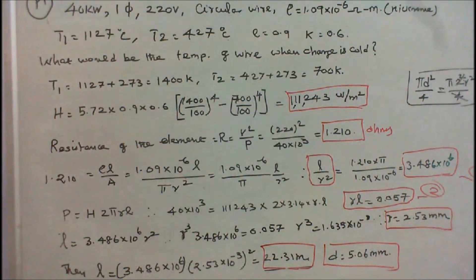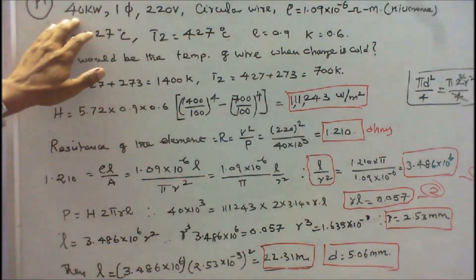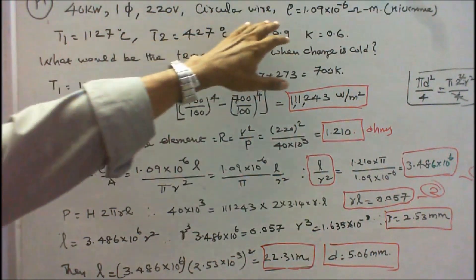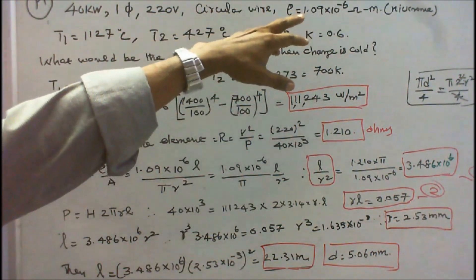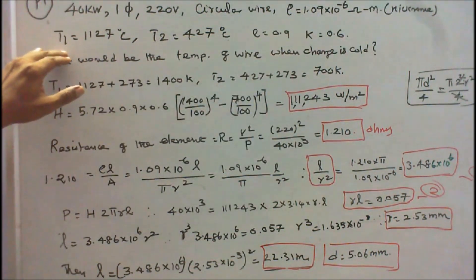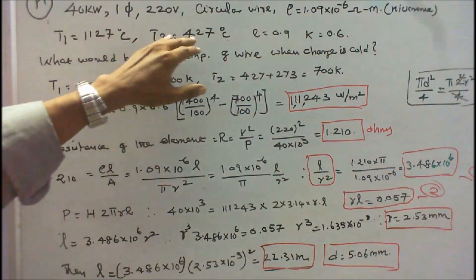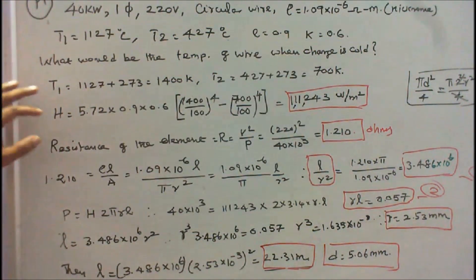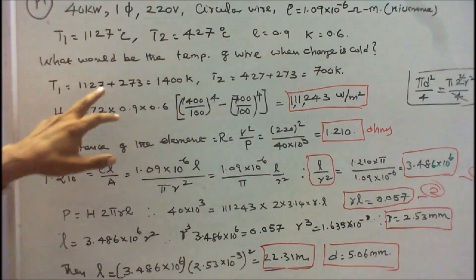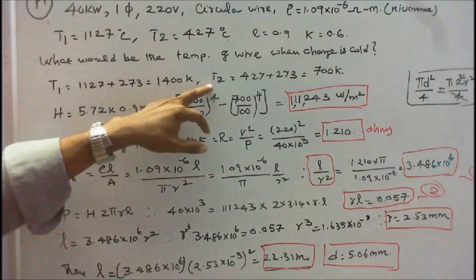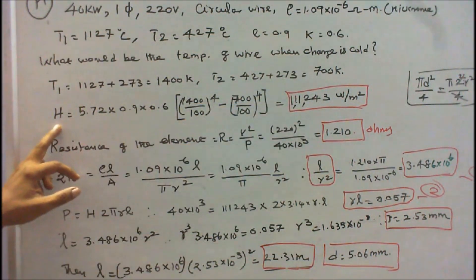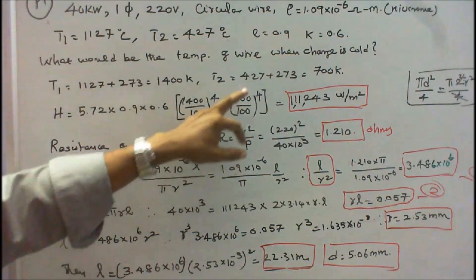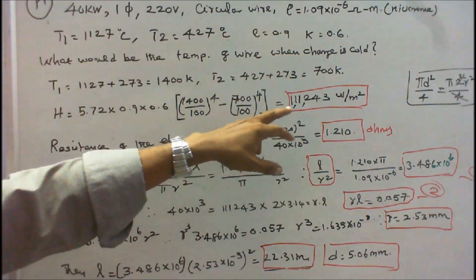In this problem, the given data are: input power is 40kW, single-phase resistance oven, supply voltage is 220V, and the wire is circular. Resistivity of nichrome is 1.09×10⁻⁶ ohm-meter. T1 is 1127°C, T2 is 427°C, emissivity is 0.9, and radiation efficiency is 0.6. Converting to Kelvin by adding 273: T1 equals 1400 Kelvin, T2 equals 700 Kelvin. Using the formula H = 5.72 × E × K × [(T1/100)⁴ − (T2/100)⁴], H equals 11,243 W/m².